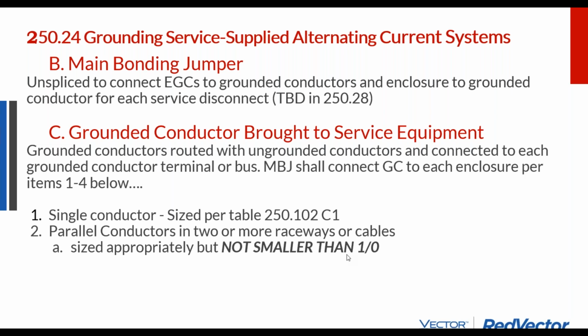And often that's not really how the decision's being made. It's more like we're installing as many big, thick wires as we possibly can to meet the application. But the code says, when can you go down and do 2 parallel runs instead of 1 larger run? The parallel runs of the same circuit for additional power ampacity are only allowed in wires that are 1/aught or larger, which is pretty thick wire. It's just 1 step down or 2 steps down from your welder's battery cable.